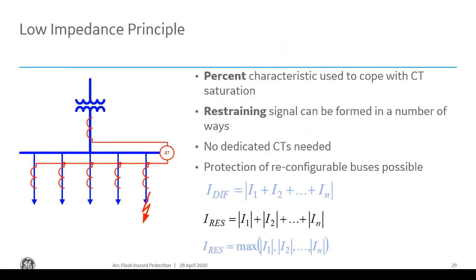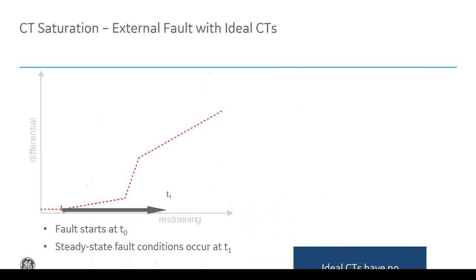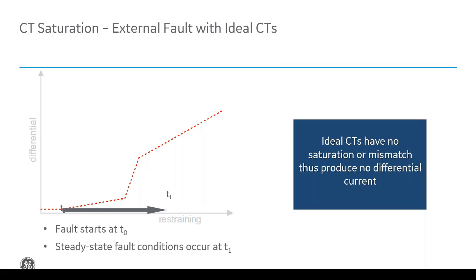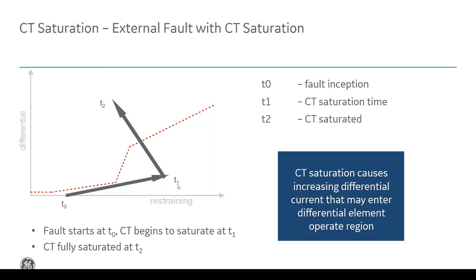As I mentioned, it's a current in equals current out principle. If the current out is not equal to the current into the bus, then we know there's an internal fault and we can trip. However, we have a percent characteristic, which we call a restraining signal. This is a diagram of what it looks like. We have a fault that starts at time t0, and then we have an external fault. You expect the trajectory to go from t0 to about t1 with no CT saturation. If there's CT saturation, initially it's going to go to t1, and then as the CT saturates, it's going to go to t2, and then into the tripping region. To mitigate this, you can see these lines here; these are slope settings in the relay. We can increase these slope settings to mitigate the effects of CT saturation, so that we can deal with external faults with CT saturation, still be able to trip reliably, and not misoperate for an external fault.